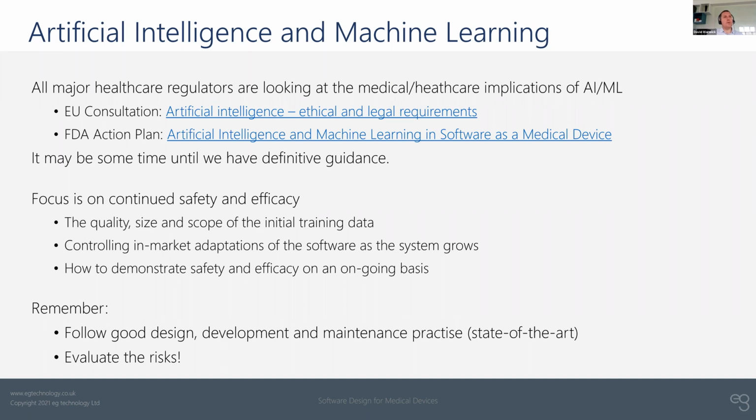So the MDR, for example, has introduced a great deal more emphasis on continued clinical evaluation of products after they've been put onto the market, particularly high category medical devices need regular updates to the clinical evaluation of their performance. My gut feeling is that artificial intelligence and ML will go in a similar way, that manufacturers will be required to provide some level of evidence that the adaptations of their systems over time continue to offer the same high levels of safety and efficacy that they did when the product was launched onto the market.